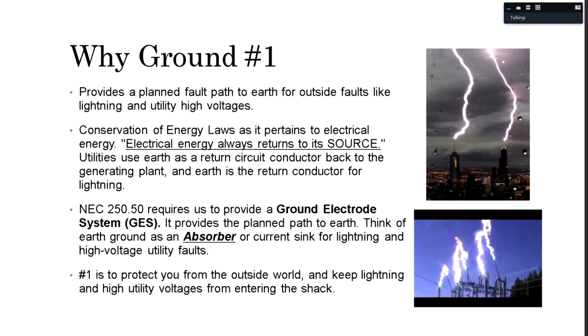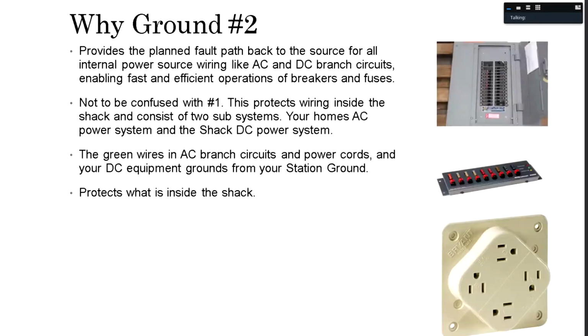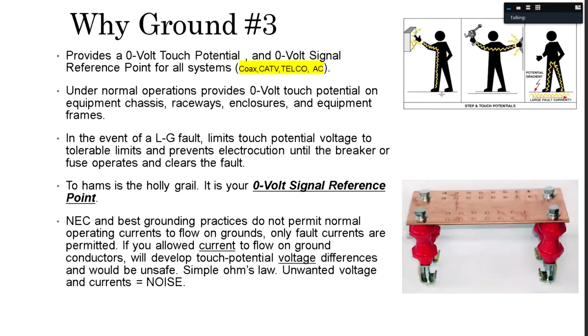So the number one reason is to protect you from the outside world and keep lightning and high utility voltages from entering the shack. Okay, number two, provides the planned path back to the source for all internal power source wiring like AC and DC branch circuits. It enables fast and efficient operation of the breakers and fuses. Let's not confuse this with number one. This protects the wiring inside the shack and consists of two subsystems: your home's AC wiring system and the shack's DC power system. The green wires in your AC branch circuits and power cords and your DC equipment grounds from your station ground protect all the wiring inside the shack. Number three, it's our 0-volt reference for everything.